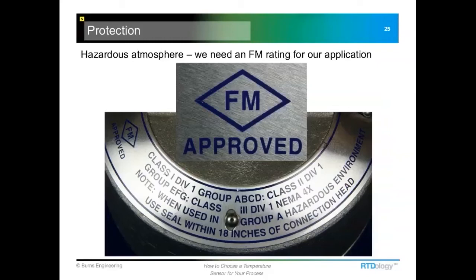And what we need for our application is one that's approved for hazardous gas environments, which for this one we're going to choose a Factory Mutual. This is a Class 1, Division 1, and this connection head actually covers groups A, B, C, and D. Now, one thing to be aware of when you're selecting a temperature assembly for a hazardous environment is that you want to make sure that the whole assembly is rated and not just the connection head.